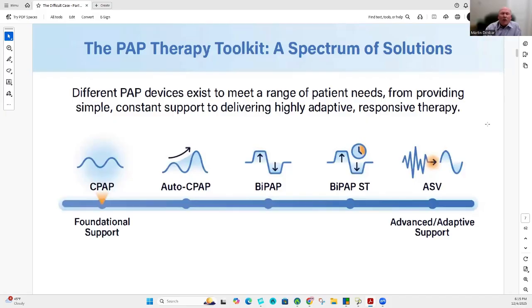The BiPAP, that's where you require so much air coming in to create the pneumatic splint that you can't exhale. It's uncomfortable. So you'll get a high inspiratory pressure, then the machine drops, and you'll have a lower expiratory. The next one is going to be a BiPAP ST. ST stands for spontaneous timed. And usually on the sleep study they'll say BiPAP ST with 5 backup breaths or 10 backup breaths. What that is, you're going to get a high inspiration, low expiration, but if there isn't an inspiration, the machine is going to breathe for you the X number of times it's ordered, 5 or 10 or 8 backup breaths during that minute or time period. So it's got backup breaths for you if you haven't breathed within a specific time frame.